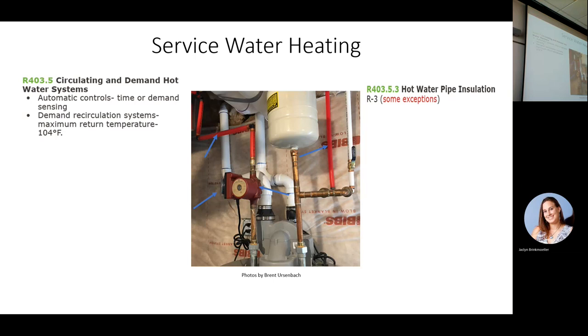Also, another point on that one, if you're doing them right, you've got a temperature sensor that will turn the pump on in addition to the timer, so it's not running all the time. So when the water cools at that point, you recirculate. It won't do it there. So insulate the loop, have a timer that you can set so you don't maintain it all night long, and a temperature control so that we just shut off if we're at temperature. We don't need to keep recirculating; get it up close to temperature and then let it set and rest. But that doesn't work unless you insulate it so that it holds the heat in the line.